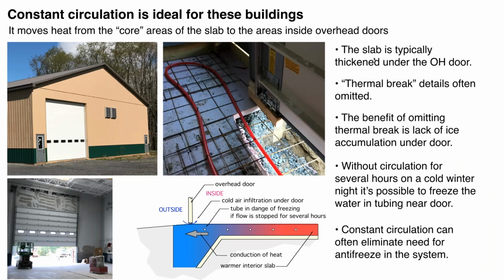Now, I mentioned earlier constant circulation. Here's an example. This is a highway garage, actually where I live. This is a relatively new building, and it's for storing snowplows. You can see we've got some large overhead doors there. And here's a detail, a photo I shot when they were building this. And you can see there's insulation under the slab. You can see the tubing there, but you can also see that there's no insulation here where the slab actually goes out under that overhead door.